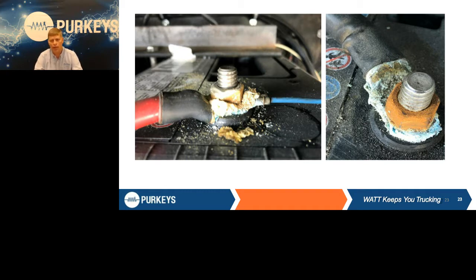You get asked a lot, well what do you recommend for a spray? I really don't care what you use, there's lots of good sprays out there. I've got some customers that just use spray paint. The only thing we're trying to do is protect the bare metal. Once we clean or load test the batteries, we want to make sure everything's clean and tight, and then apply grease, paint, dielectric grease, whatever you use in your shop. We're just trying to protect that bare metal from corrosion.